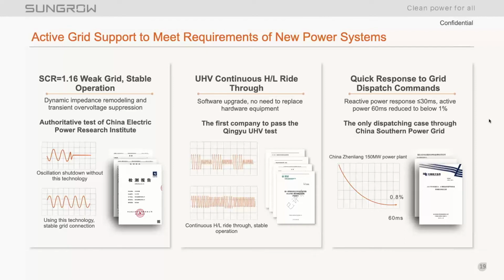And quickly, we've discussed the active grid support to meet the requirements of new power systems. This is just kind of a quick visual about what that means, right? So we talked about the short circuit ratio getting down around 1.16. Definitely areas globally are experiencing reduced strength in the grid because of these emerging technologies. And it's up to the renewable energy providers, most especially in solar, wind and energy storage, to be able to provide dynamic support to strengthen the reliability of the grid, because we are by a far margin the biggest slice of the pie when it comes to new power being brought online. So it is our responsibility to help improve, not maintain, the stability of the grid.